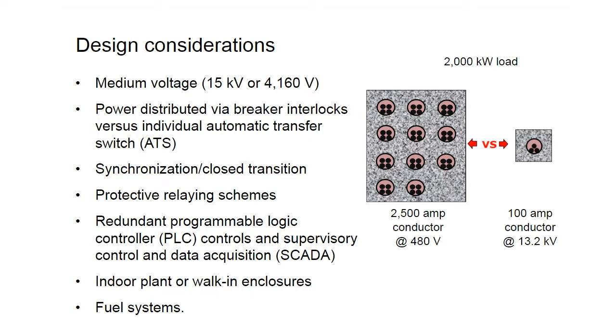Some of the other design considerations: because data centers are a large electrical load, using medium voltage generators, 15 kV, 4160, trying to get that transformation closer to the load is a good option. You can see on the right there is an example of what a 2,000 kW load would look like from a 480 standpoint versus a 13.2. So if you're running underground with feeders, you have to upsize for ampacity reasons for the heating. You could be looking at 11 sets of feeders versus one set at 13.2. So it's a huge cost savings to go to 15 kV.